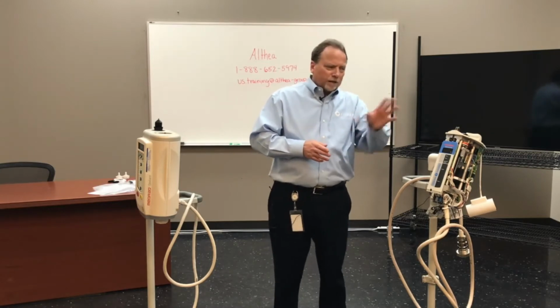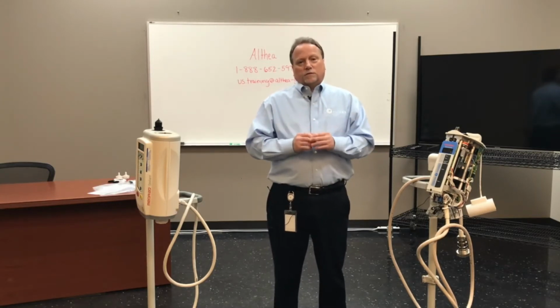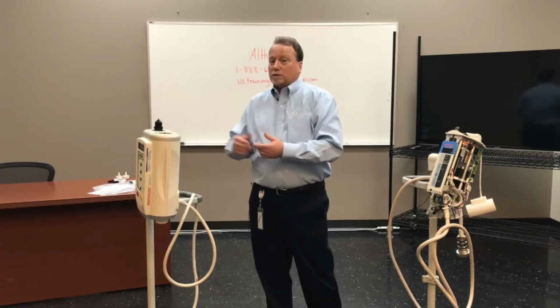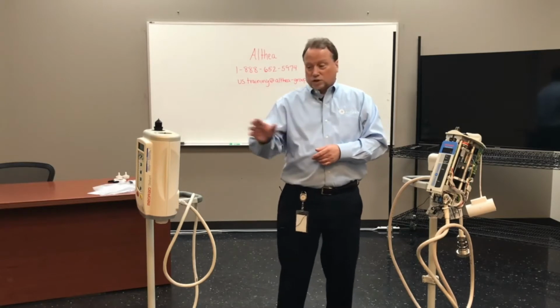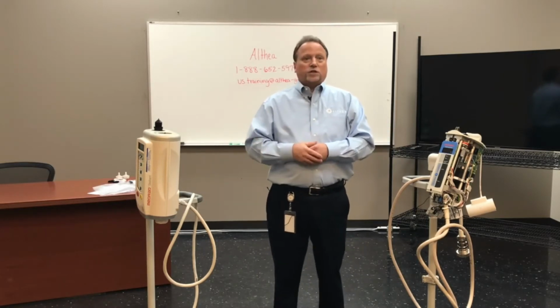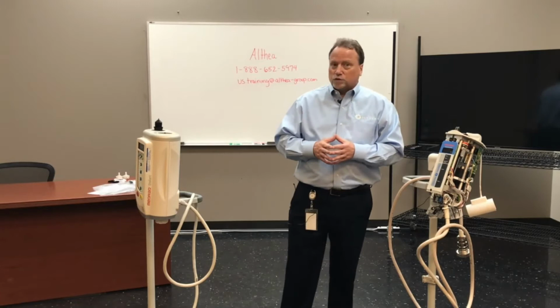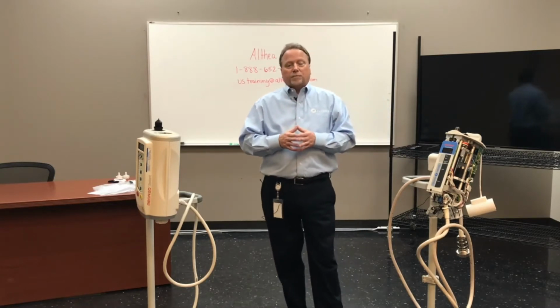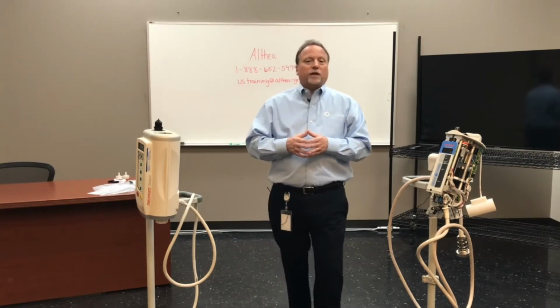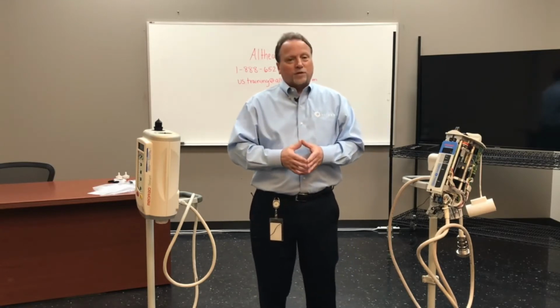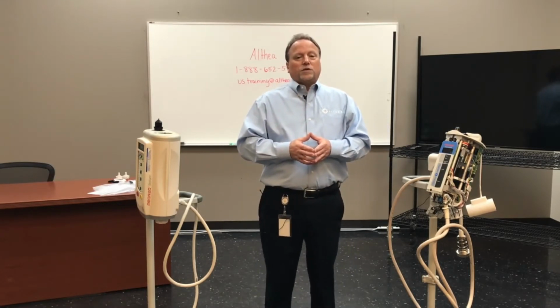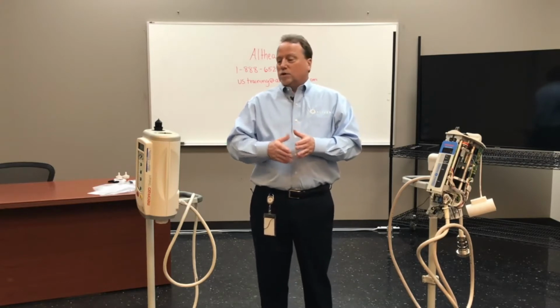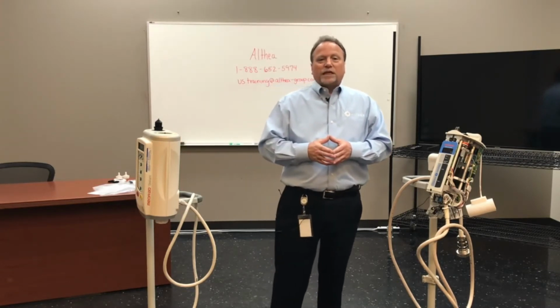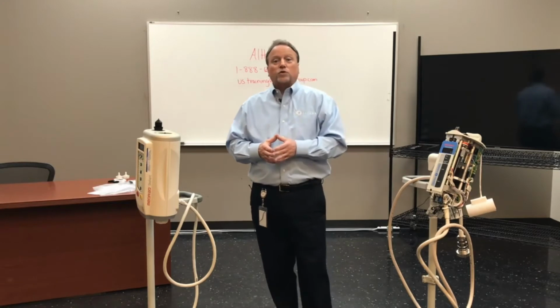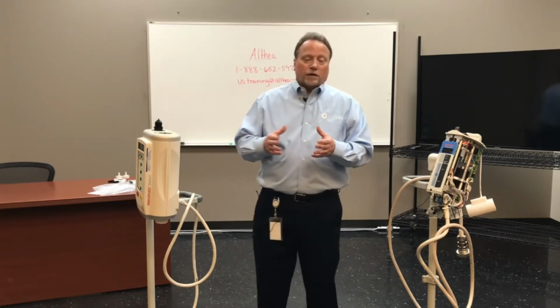There is no sense of doing a PM on a broken piece of equipment. Well, they're getting by without it, that's no problem. No, fix it, because there may be other problems that one problem is hiding. It may go deeper than just that one problem. So fix the injector. Resolve the issues first before beginning the PM. And that's why you contact your customers at the beginning of the month when you know your PM's coming due, so that you have a chance, a time to correct the problems.